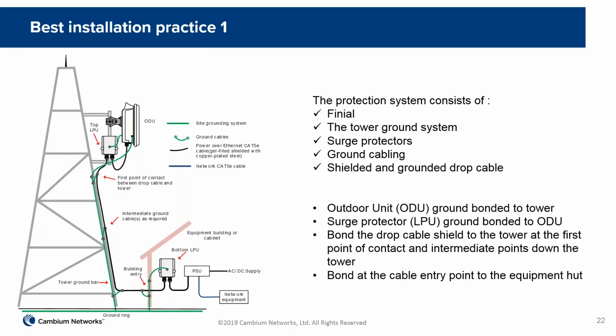So we take all those things together. We have the lightning protection unit, surge suppressor of some form. We have cable shielding. We have a radio which has a known withstand voltage. Those components in themselves will help us to get a good, robust, resilient system. But it's important that we connect them up correctly, and it's important that we site the radio, that we site the equipment itself correctly.